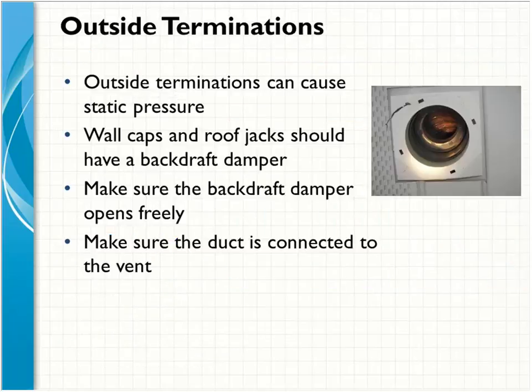Where we're putting that termination is important too. A lot of people don't like to poke holes in the roof and create opportunities for leaks, so we see a lot more terminations in the soffit. And the soffit is usually the quickest way out of the building, which helps us keep the ductwork short and straight. But we have to be aware of where we're putting it.